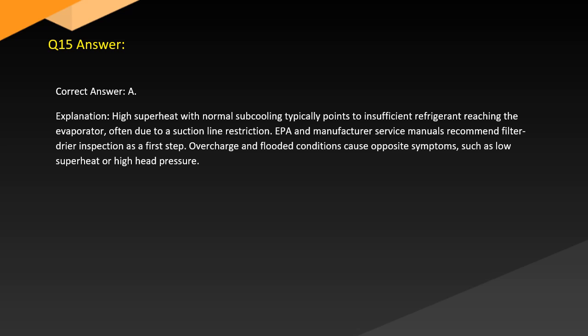Answer. Correct answer: A. Explanation. High superheat with normal subcooling typically points to insufficient refrigerant reaching the evaporator, often due to a suction line restriction. EPA and manufacturer service manuals recommend filter dryer inspection as a first step. Overcharge and flooded conditions cause opposite symptoms such as low superheat or high head pressure.